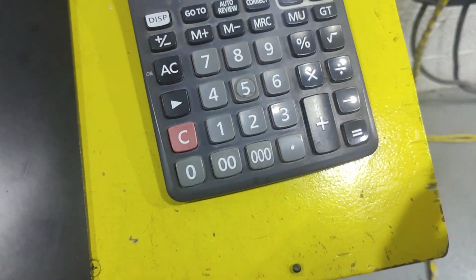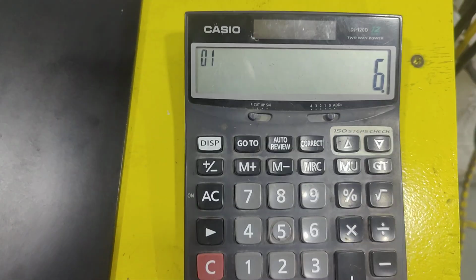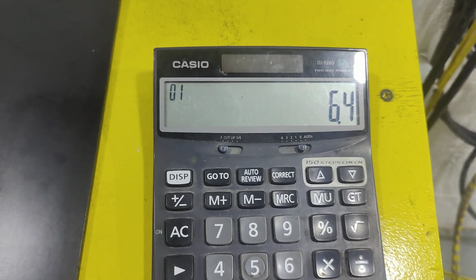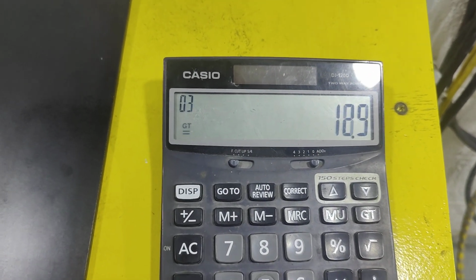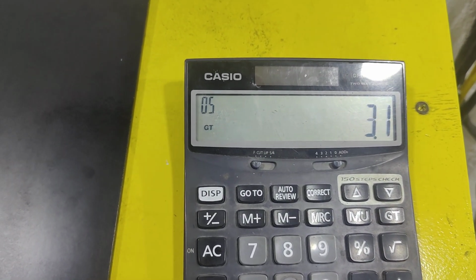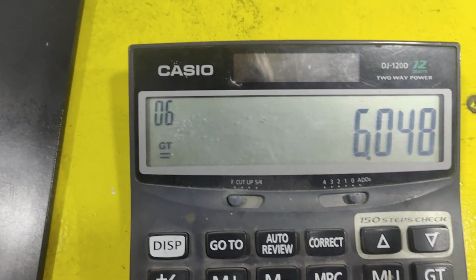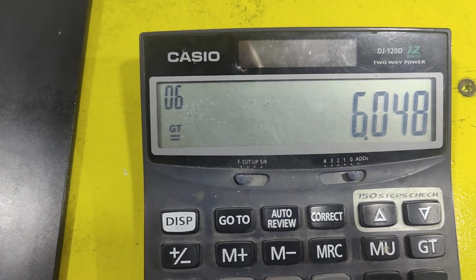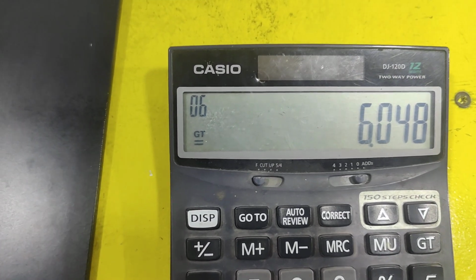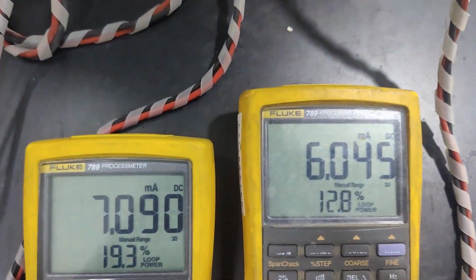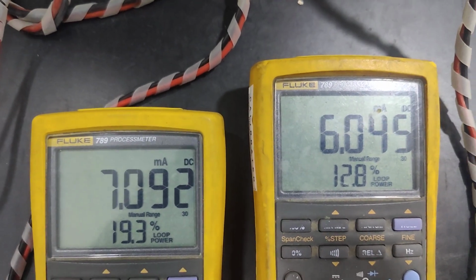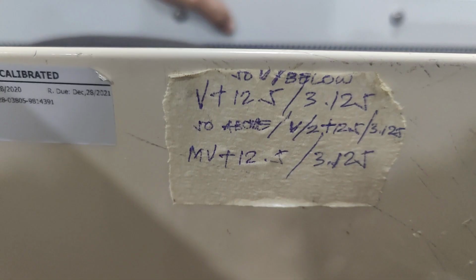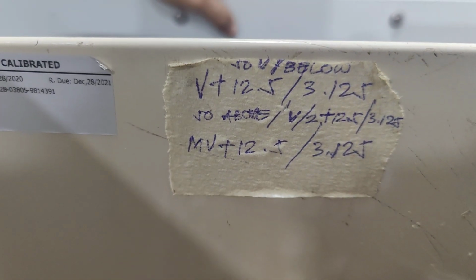Okay. For current also, the millivolts we measured is 6.4, plus 12.5, divided by 3.125. So 6.048 we need to get in the current transducer output, and the same we are getting here, 6.045. One important consideration that needs to be made here.